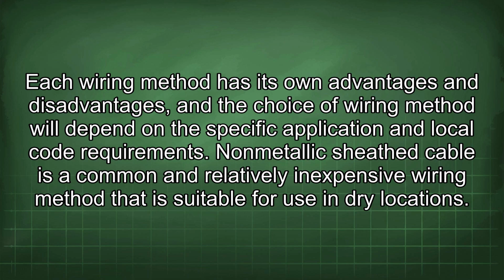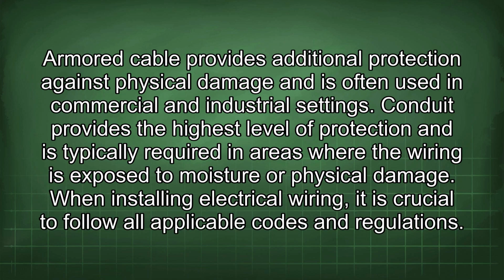Non-metallic sheathed cable is a common and relatively inexpensive wiring method that is suitable for use in dry locations. Armored cable provides additional protection against physical damage and is often used in commercial and industrial settings. Conduit provides the highest level of protection and is typically required in areas where the wiring is exposed to moisture or physical damage. When installing electrical wiring, it is crucial to follow all applicable codes and regulations.